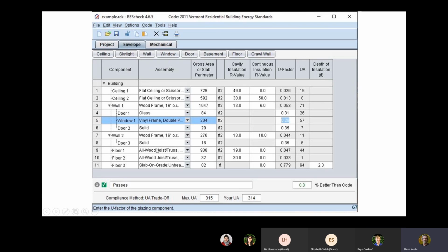And then same thing with the floors, drop-down menu, square footage, R value. If you had an exposed slab edge or basement wall, you would do that. This is your slab on grade here. So this is probably, I'm not sure what this is, but it's slab on grade for a portion of the house. Looks like it's over unconditioned space for this floor. I'm not sure exactly what that assembly is. But anyway, you describe all of the pieces of the thermal envelope. There's more room here than it looks. You can make a lot of lines if that's what it takes.